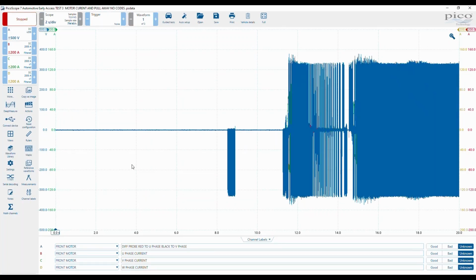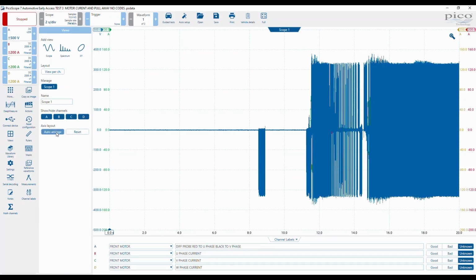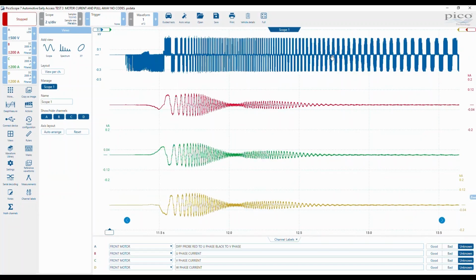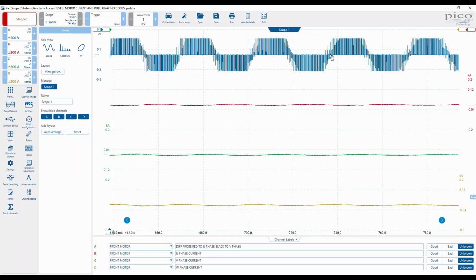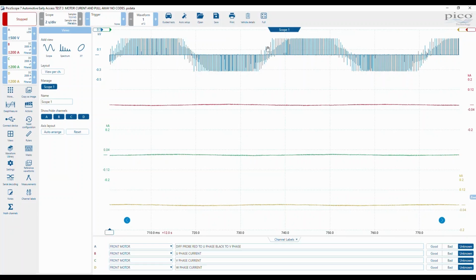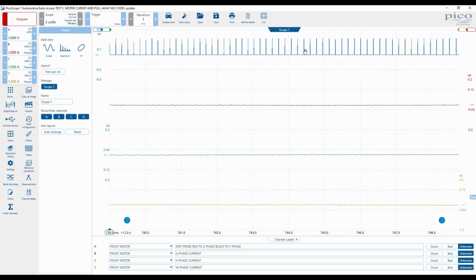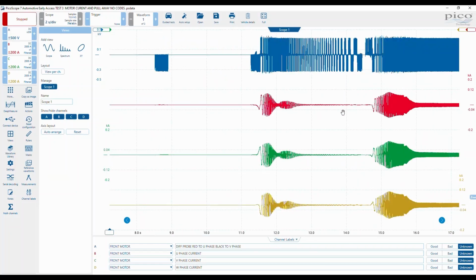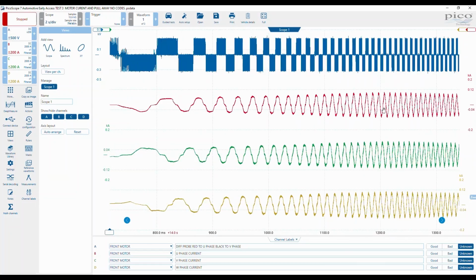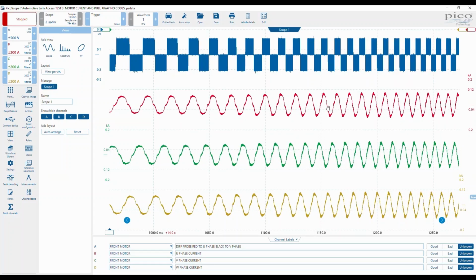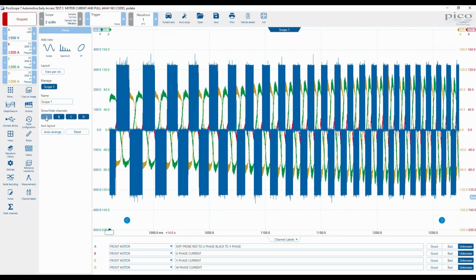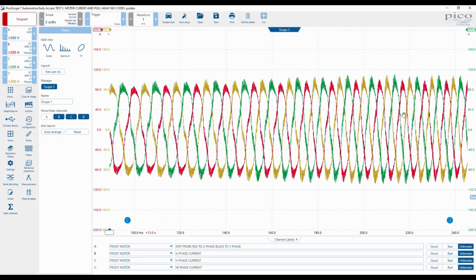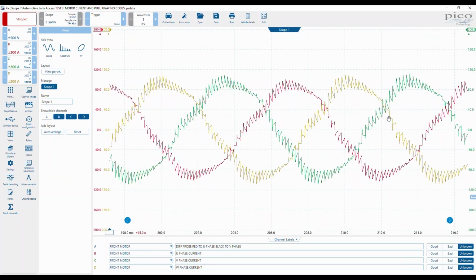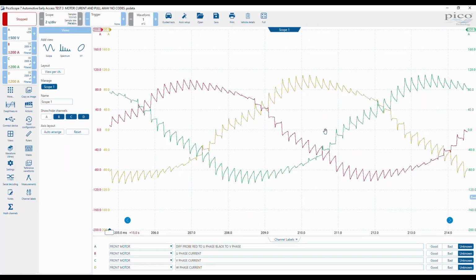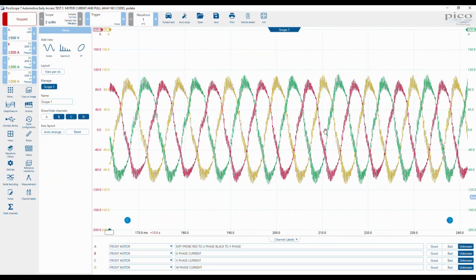Okay, let's have a look at this waveform in a little more detail. We'll use the views and auto arrange. Voltage phase to phase is kind of what we'd expect to see. Uniformity is there. And let's have a look at current, more importantly, and phasing. If you remember, we were looking at, in fact, let's reset and hide channel A, so that way we can see just how the phases align. They've still got that sawtooth pattern, as we'd sort of highlighted before. So that was a bit of a red herring.